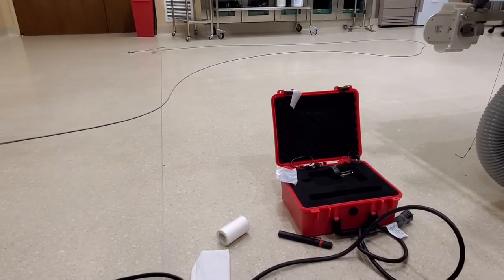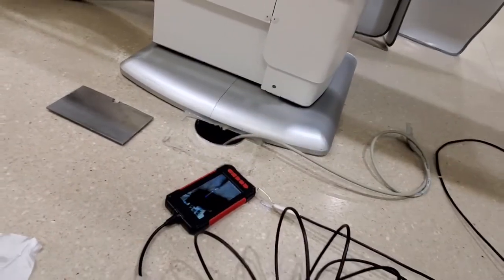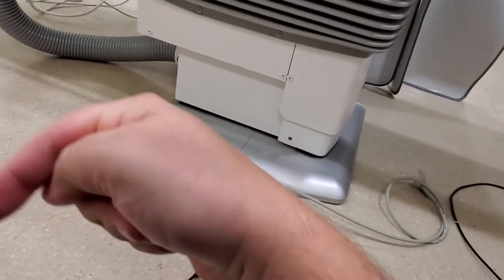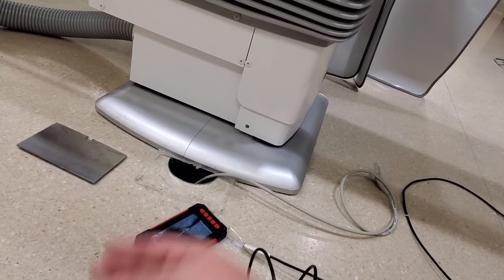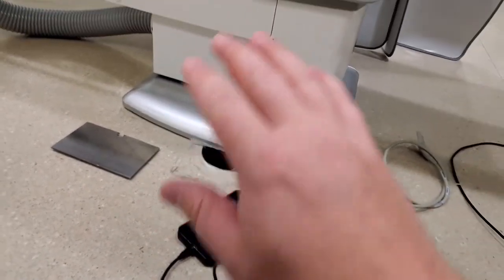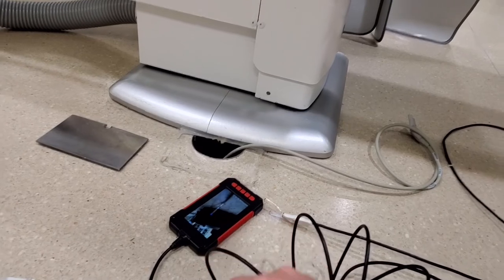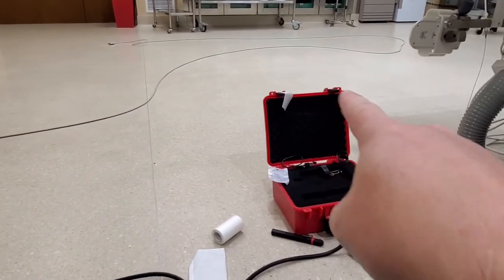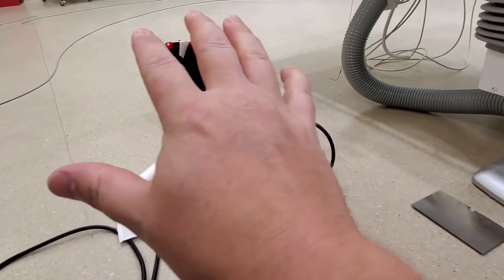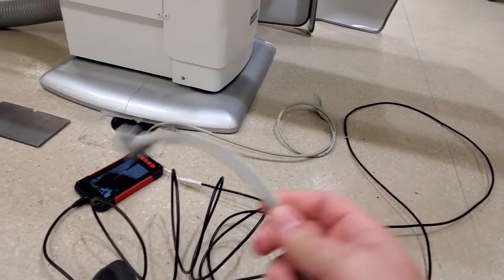The first rule of running cable is if you're not working off a spool, spread out your cable. You can see I got it all spread out and wrapped up here, and I'm ready to tape it because we're going to use the old cable as a pull to pull the new cable in reverse down through the hole into the control room. Don't cut your cables — ever, ever, ever. Always use them as a reverse pull to go down through. You can tell this looks like a four-inch conduit, so I'll have plenty of space. There are some obstructions down there and I'll have to fish it around a little bit. The one thing I can prevent is binding of the cable and make sure the cable doesn't drag anything else down the hole. So I'm going to clean up this area, get it out of the way, clean everything around this hole, and we are going to tape that cable to this one.